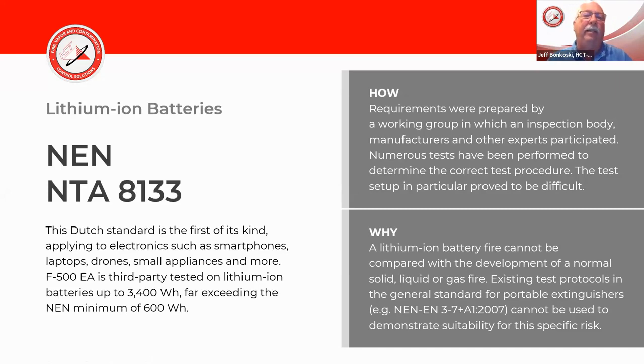There's an NEN NTA 8133 standard created by the Dutch. They developed it trying to find a solution for lithium-ion batteries, to see if there was something that could work in a fire extinguisher to deal with fires in buildings, scooters, or other small applications. So they created this test protocol, a test standard with listings and markings for an extinguisher, where if you pass the test, you can get an extinguisher marked and listed for use on lithium-ion batteries.